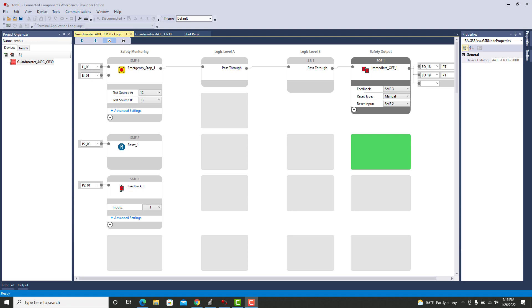Let's start where we left off in the last video. This was the configuration that we had, and we had no logic for level A or level B. We went straight from safety monitoring to normally closed contacts for the emergency stop. We had a reset and feedback, and we were driving a safety output which is an immediate off. The immediate off outputs 18 and 19 are connected to K1 and K2 contactors. You can get safety relays that have force guided contacts or you can get safety contactors where you have force guided contacts for the status of the relay and the contacts that you're actually controlling three phase 480 to a motor or something.